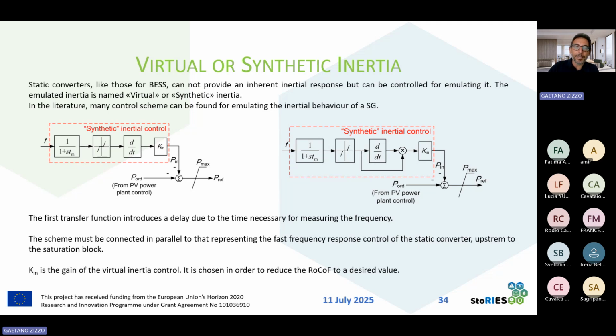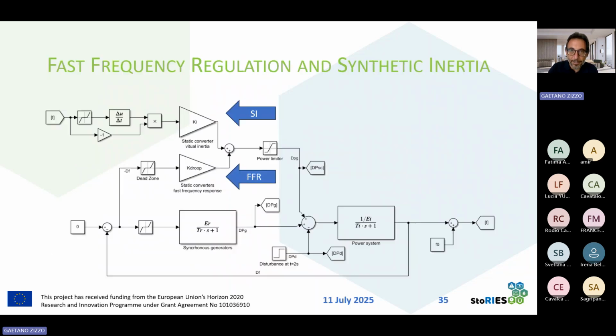If the given dead band of the frequency is not respected, the frequency is derived, and the derivative is multiplied by this gain that represents the virtual inertia of the system, and an amount of power is injected into the system in the very first seconds from the disturbance, simulating the natural response of a thermal or usually of a rotating machine.